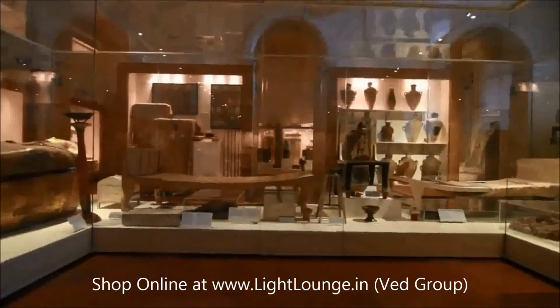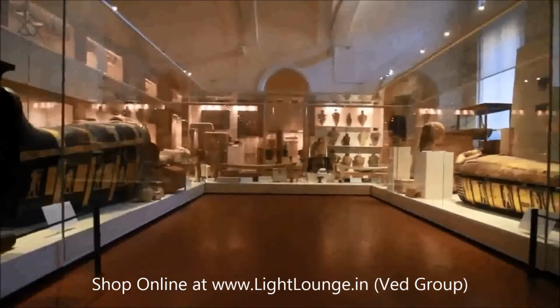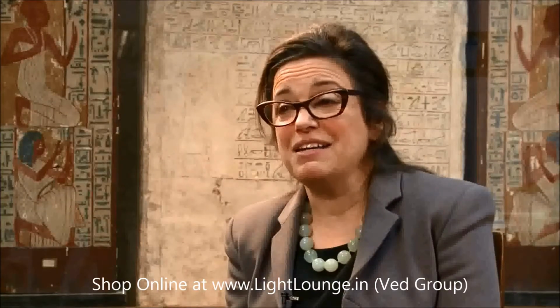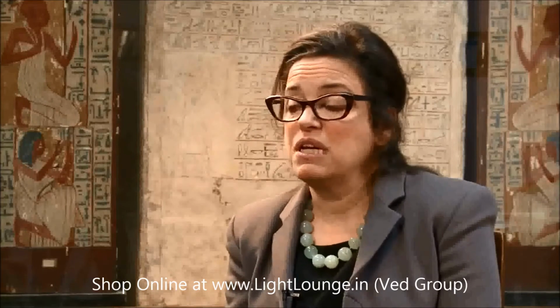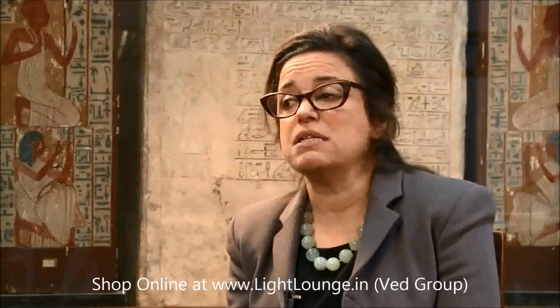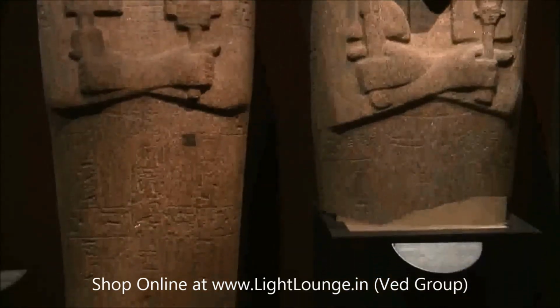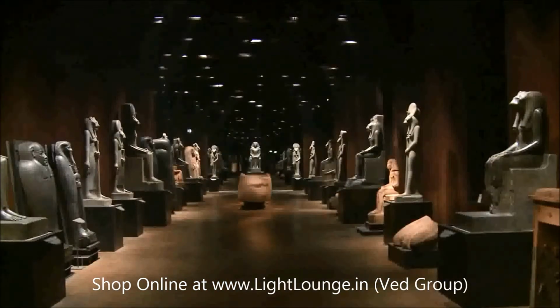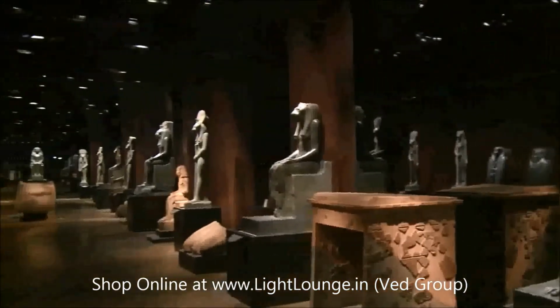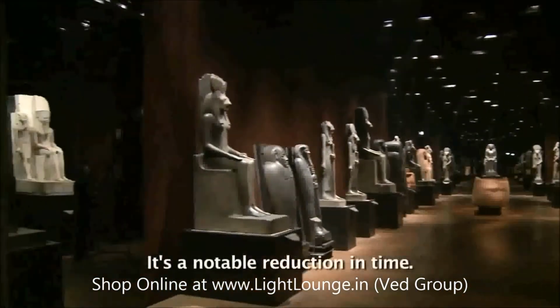Consumption is down, and that's a good thing. In the Tomb of Ka, we were burning almost 2,500 watts of lights. We now have 250 watts of light in both the Tomb of Ka and in the Old Kingdom Gallery adjacent to it. So that's quite a savings. Plus, as I mentioned, we're not generating as much heat, as much dust. In the statuary, we've gone down by about 8,500 watts. Now, you take both together, we're talking about almost 600 euros per month, just in those two galleries.